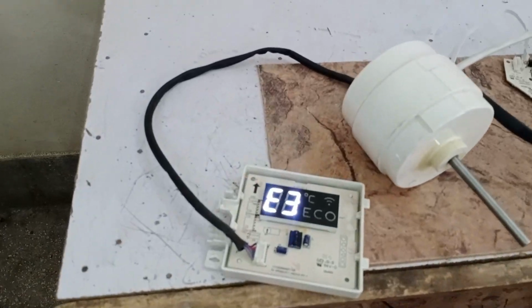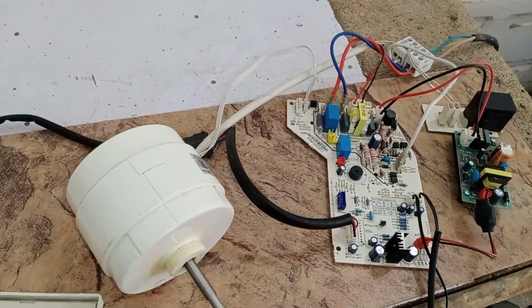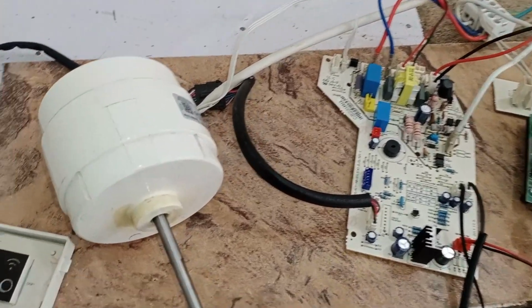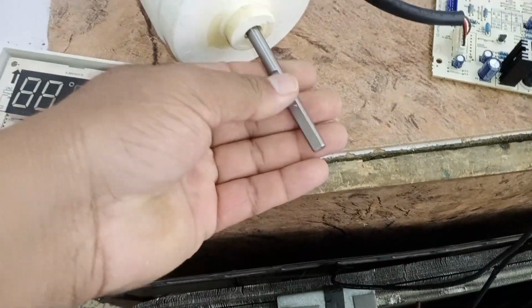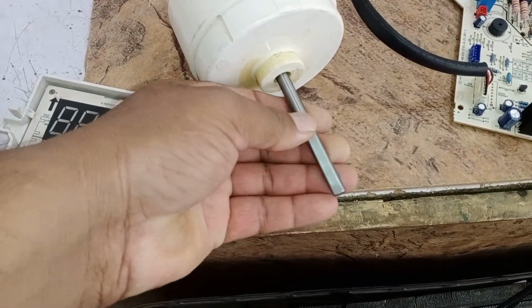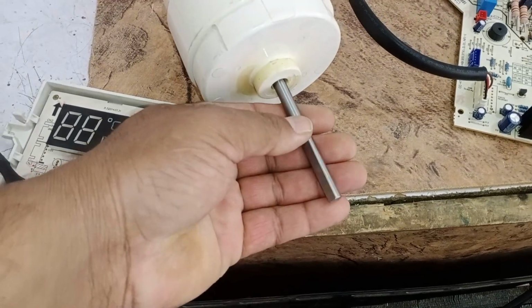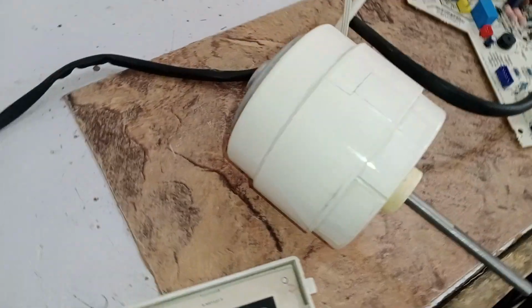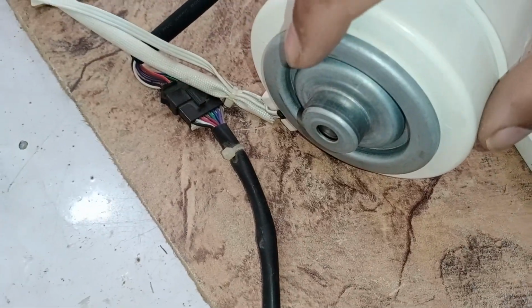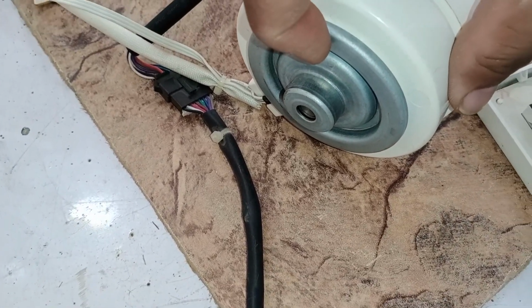Now, the next error code we're seeing is E3. Whenever the E3 error occurs, it is usually related to the fan motor. If the fan motor gets jammed or becomes too stiff to operate, this issue will arise, as it will fail to generate proper feedback. I've already created a detailed video explaining this issue, including the motor's circuit. By watching that video, you can resolve the feedback issue.